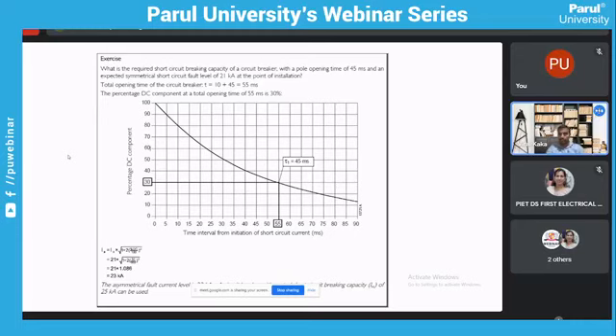So breakers are normally checked twice. Suppose your percentage DC component while breaking is higher. Normally, as per practice, it will vary between 36 to 49% for the primary switchgears, and sometimes 36% DC component is left on the circuit, but that is as per the type tested reports for the secondary gears. But if the percentage DC offset is quite high, that is where factories again check with their R&D team and then confirm whether the breaker is actually suitable for that sort of application or not.